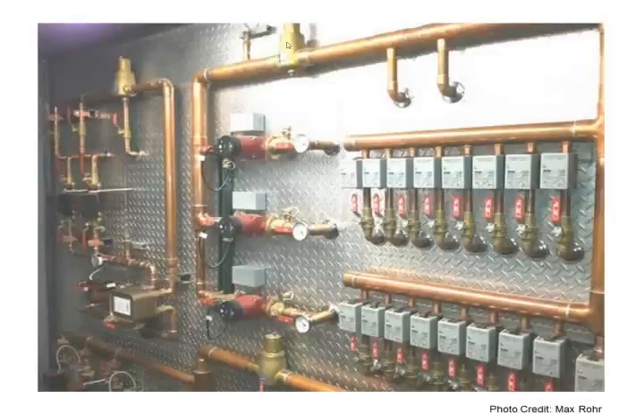We'll talk about that. Expansion tanks. I don't know too much about this job. I don't see an expansion tank, but if I look over here, I see another air separator and something connected to it. And knowing that expansion tanks and air separators like to live on the low pressure side of the system, I'm going to guess on the other side of this wall is an expansion tank. So where do we put our expansion tanks to allow the system to be most effective? What happens to an expansion tank if it becomes ineffective, if it becomes waterlogged? What does it do to the performance of the system? What if we took this isolation valve here and isolated the expansion tank? What's the effect of that, whether it's done on purpose or accidentally?